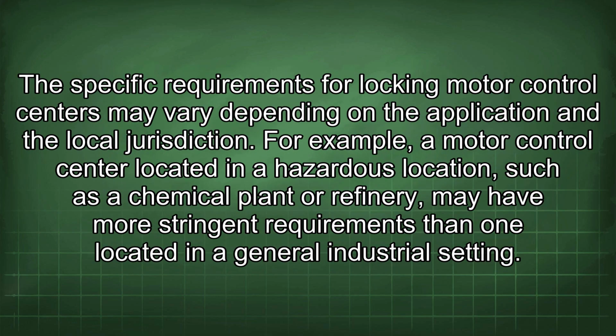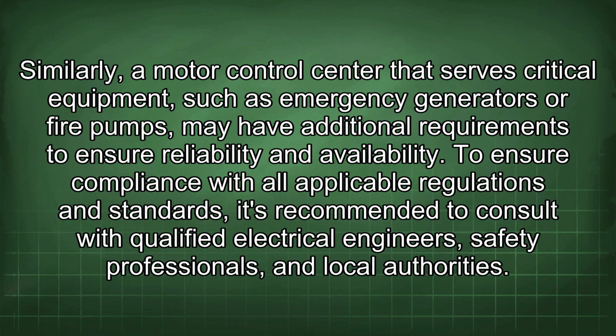The specific requirements for locking motor control centers may vary depending on the application and the local jurisdiction. For example, a motor control center located in a hazardous location such as a chemical plant or refinery may have more stringent requirements than one located in a general industrial setting. Similarly, a motor control center that serves critical equipment, such as emergency generators or fire pumps, may have additional requirements to ensure reliability and availability.